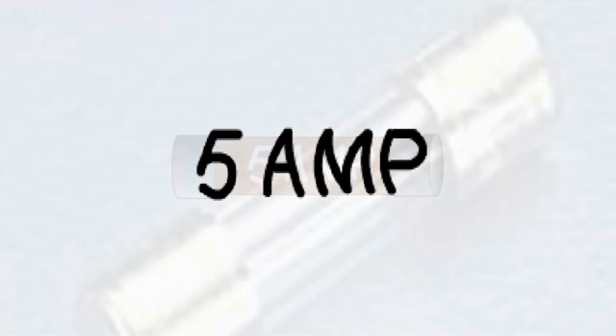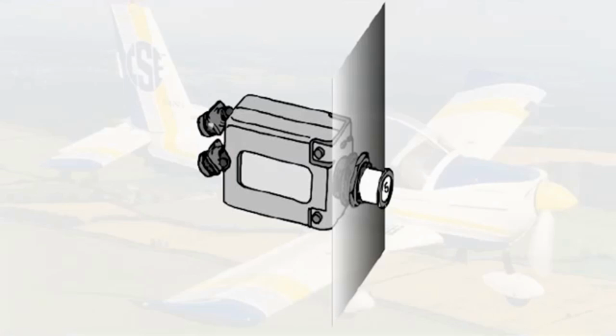Fuses which have a greater rating than that specified for a particular circuit must never be used. The consequences will most probably include greater damage being caused and may be an electrical fire. Circuit breakers are fitted, as are fuses, to protect equipment from overload or fault conditions. They incorporate a heat-sensitive tripping device and a manually operated trip reset switch.